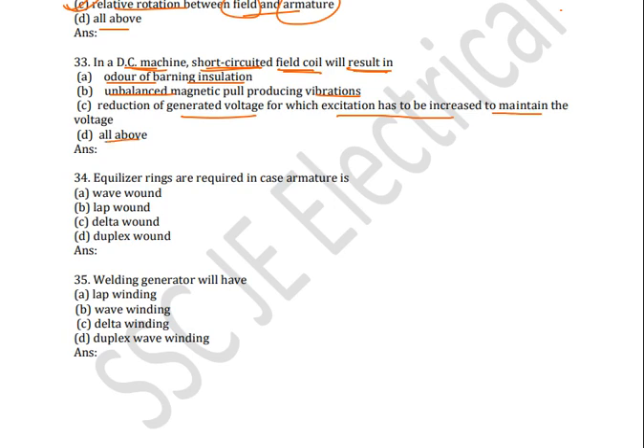If you know the answer, just answer in comments. The correct answer is all of these. When field coils get short-circuited, there will be odour of burning insulation — the insulation will burn and smell will come out. There will be unbalanced magnetic pull producing vibrations — the machine will vibrate. There will also be reduction of generated voltage, for which excitation has to be increased to maintain voltage. So D — all of these — is the correct answer.